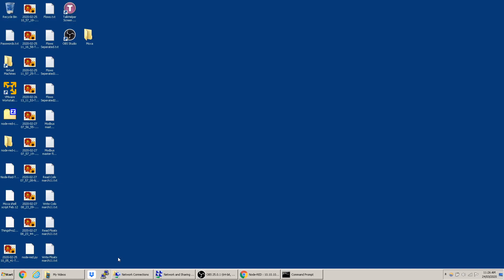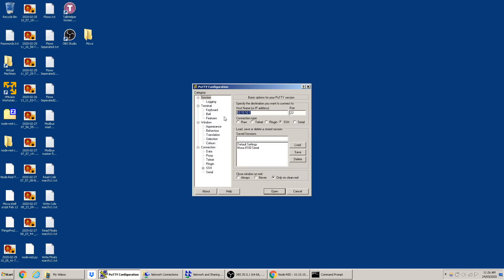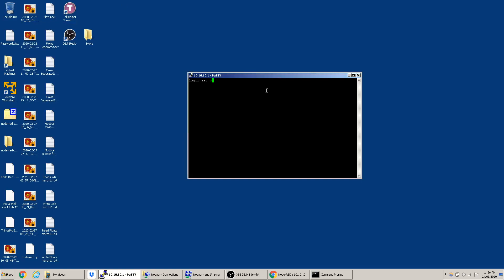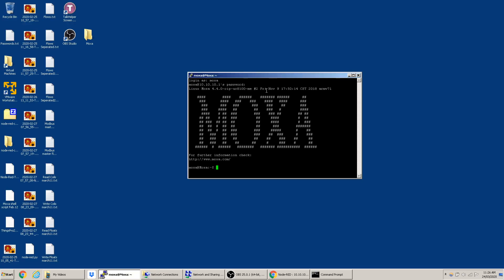The first step to logging into the Moxa is opening PuTTY. Enter the IP address of the LAN port you're connected to, port 22, and select SSH. Hit open, the screen will pop up, and log in as 'moxa' — the password is also 'moxa'. This is what it looks like when you're logged in.